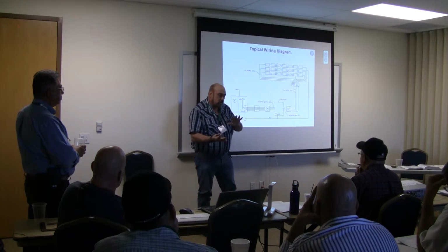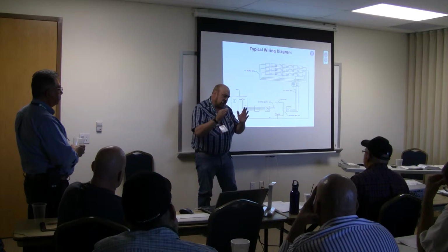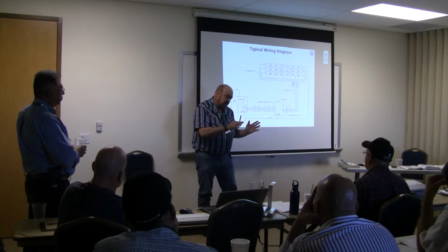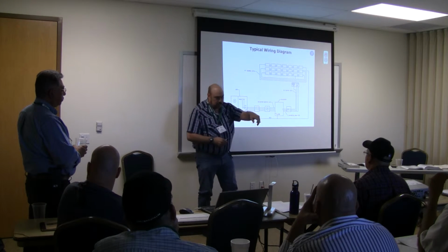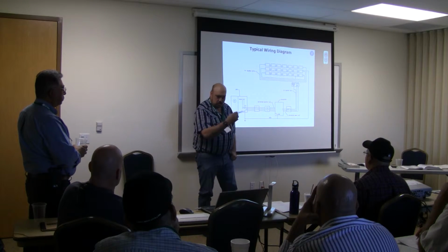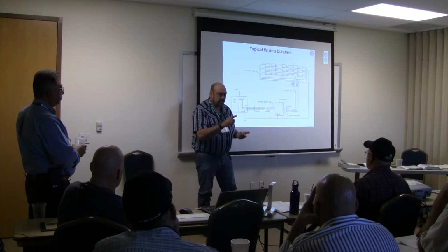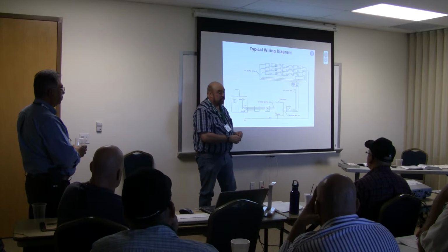It's a more accurate way, and it'll actually bring down that total VOC less than what table 690.7 gives. A lot of guys will just go ahead and use table 690.7, and that's a good way to do it, but it never can exceed 600 volts.